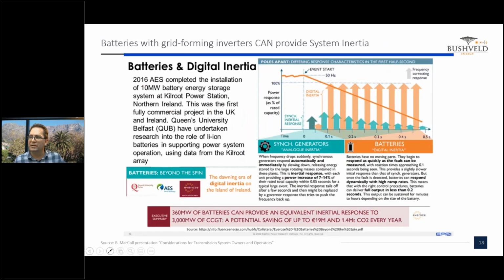I put in a slide about inertia, since that's been a big topic of discussion recently - whether inverter-based technologies can provide the right level of inertia compared to synchronous generators. We're starting to see that the newer generation of grid-forming inverters can do this, and very fast. What's exciting is that for the same amount of capacity they can provide significantly more inertial response. You can see the orange comparing a same-sized inverter-based system to a gas system, and the conclusion from this report by Fluence was that it's almost 10 times as much inertial response that can be done by power electronics, by inverters, rather than by synchronous gas.